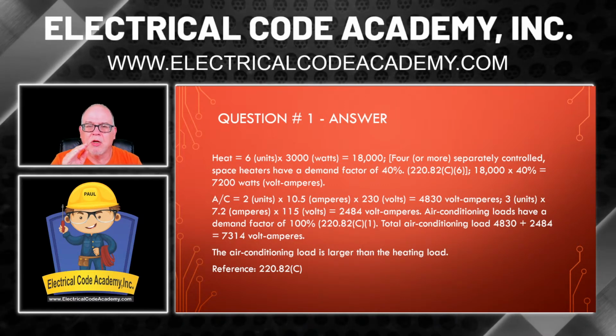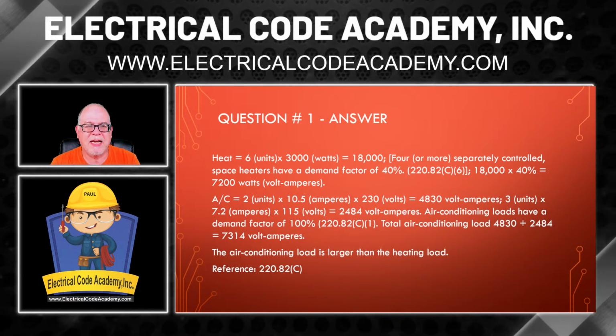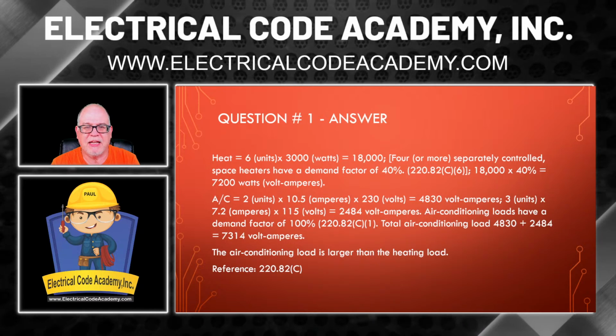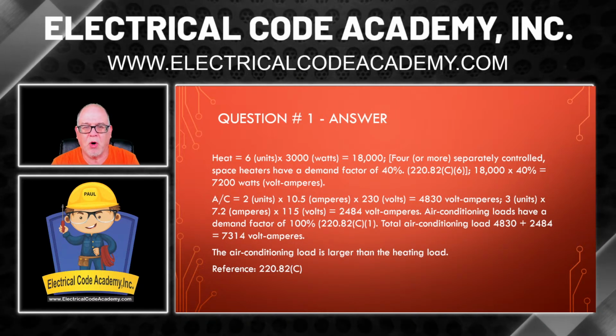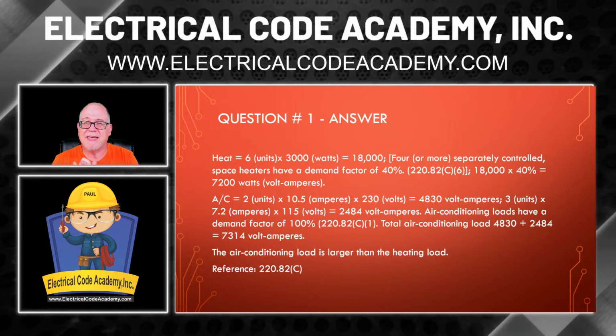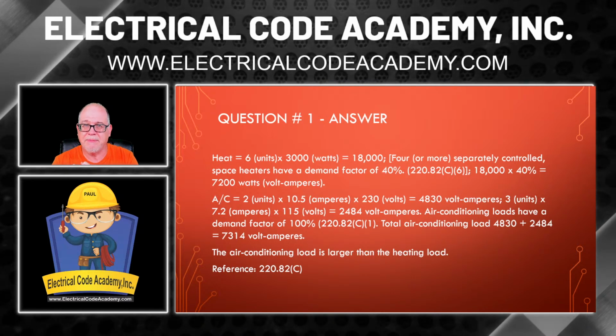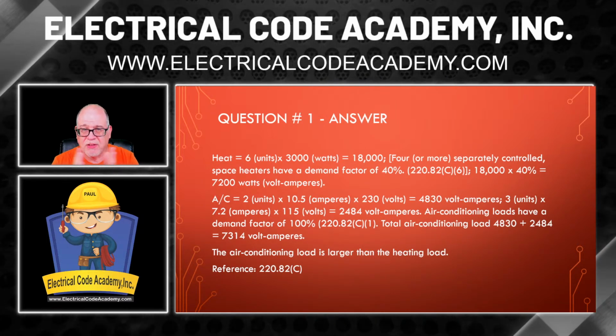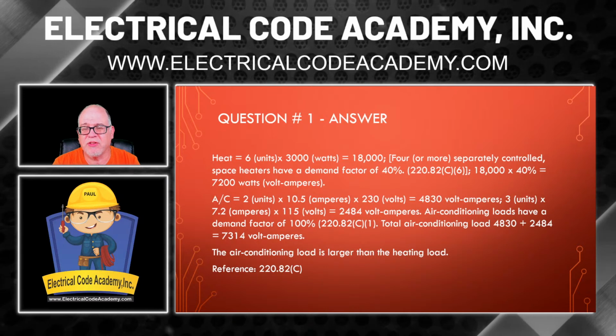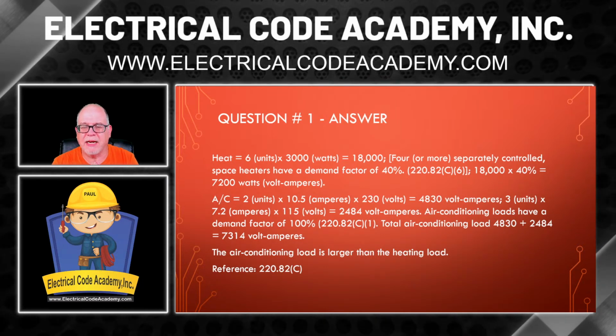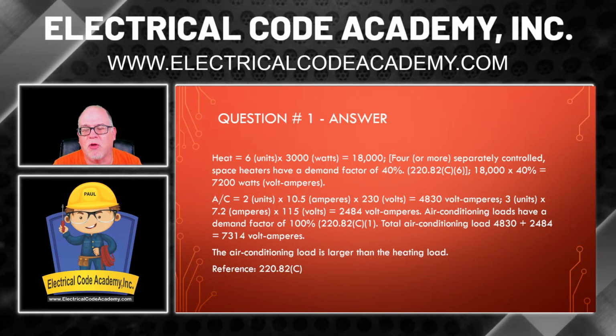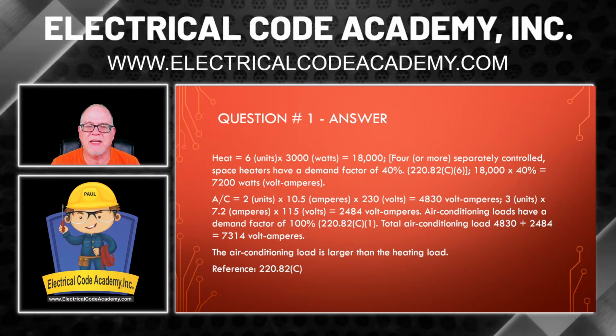All right. So now we want to do 3 times 7.2 times 115. That's 2,484 VA. So all we're going to do, remember, is we take them at 100%, right? So we're going to add the 2 together: 4,830 plus the 2,484. That's 7,314 VA.